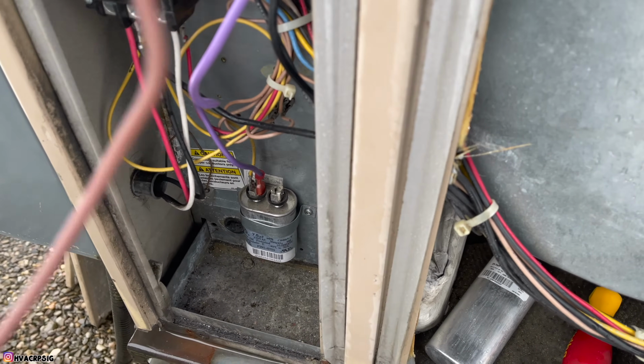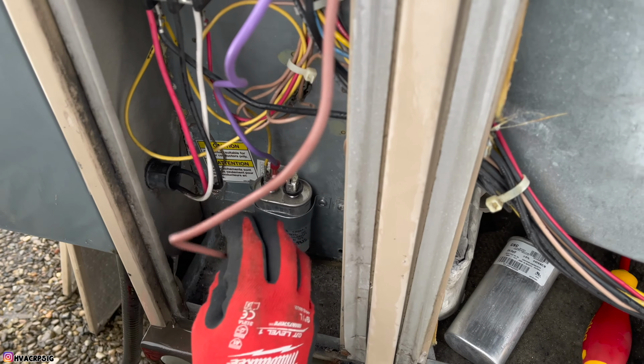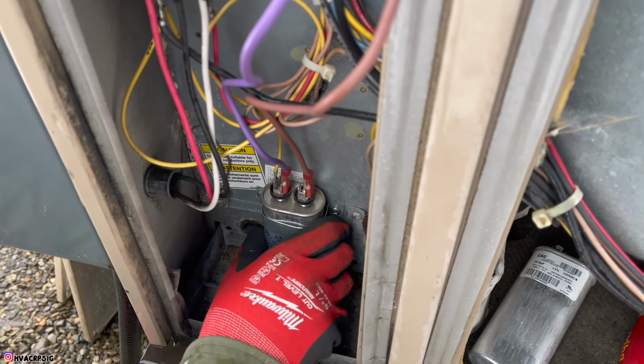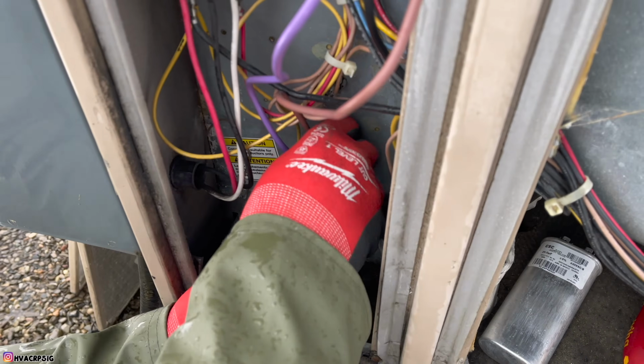Just briefly, why don't you explain what the capacitor is doing on this style motor? Well, this would be the same as your furnace blower, a permanent split capacitor motor, right? It's got a parallel with the run winding.